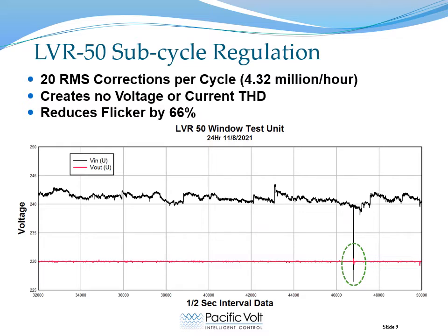Many manufacturers claim some sort of sub-cycle regulation in their marketing literature, but the details tend to get pretty vague as you dig into it. We, however, are happy to disclose exactly what we mean. Our regulator changes its duty cycle 20 times every cycle, which means it changes the output voltage 4.3 million times an hour. We can do this without creating any voltage or current total harmonic distortion, and it's fast enough to reduce flicker as measured by the PST value by an average of 66%.